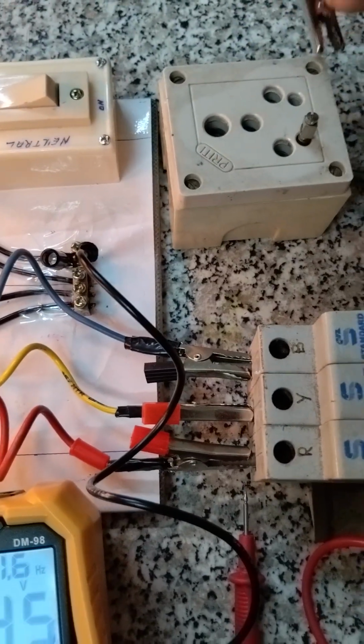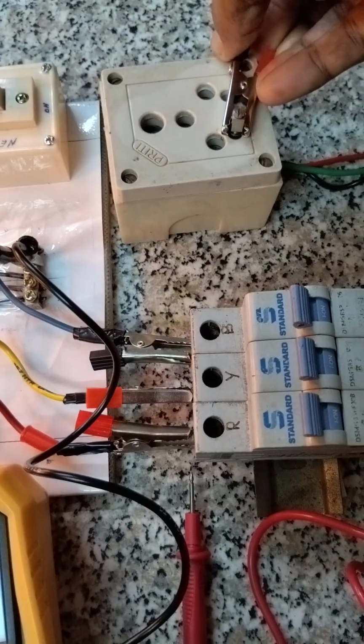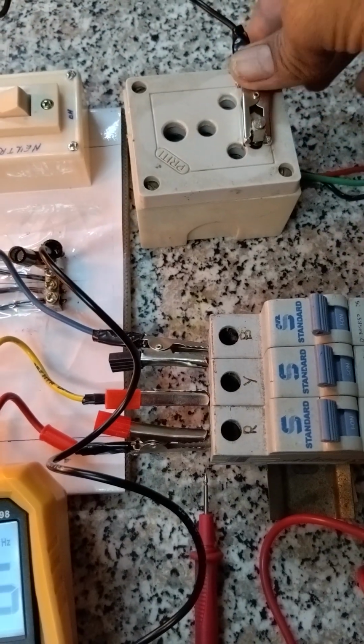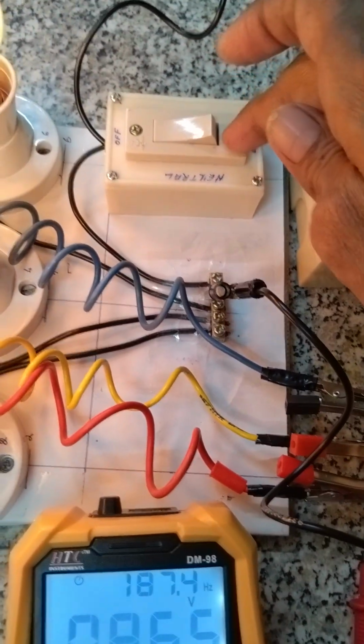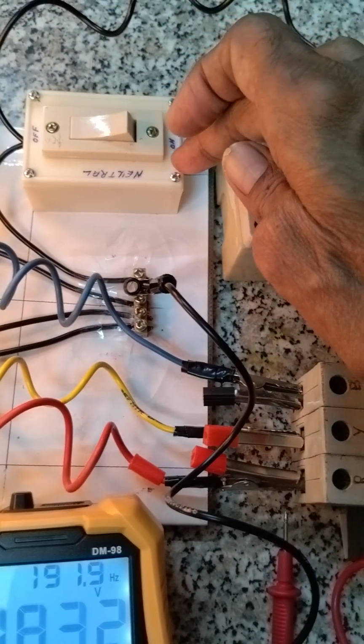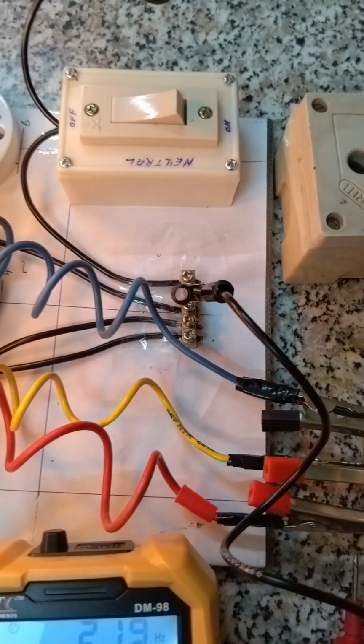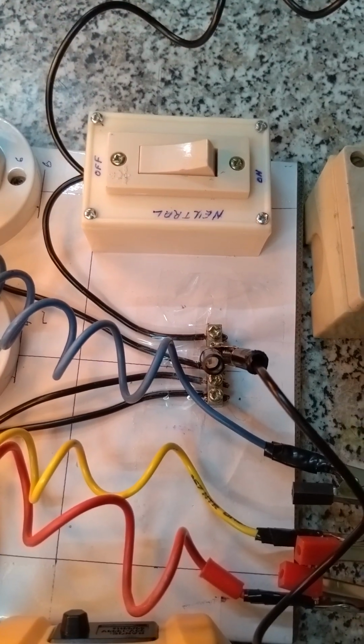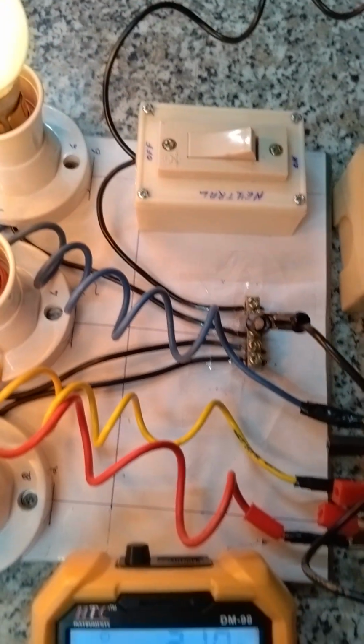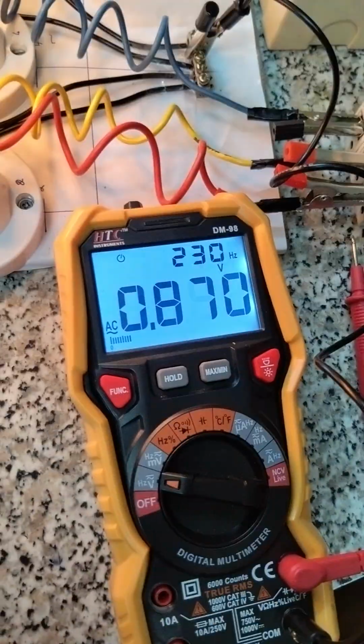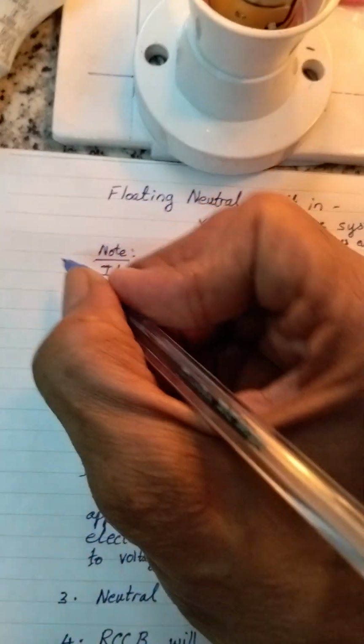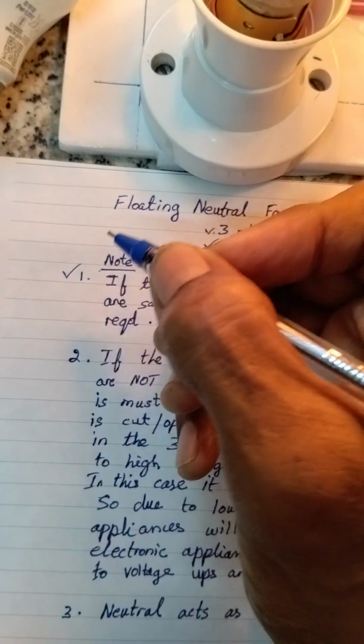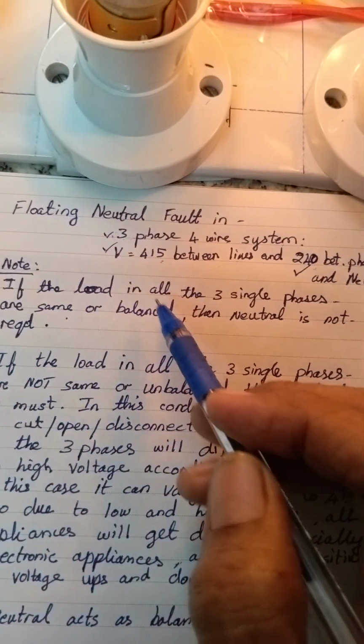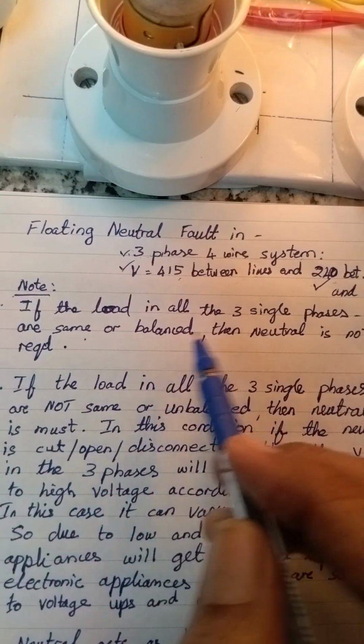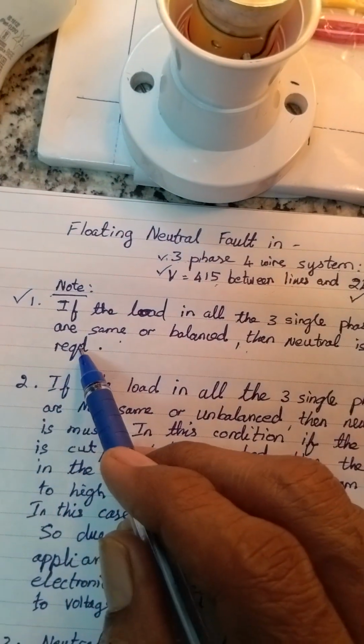Now what I will do is I will connect the neutral. There's no need to remove this, but for clarity I have removed this. This switch itself will do this work of connecting and disconnecting. So this point we have checked. That is, if the load in all the three single phases are same or balanced, then neutral is not required.